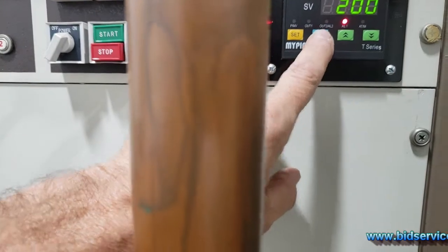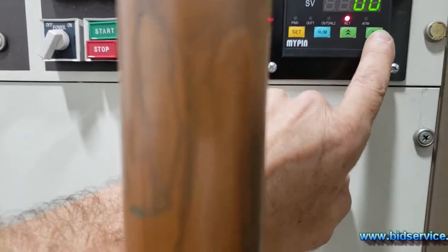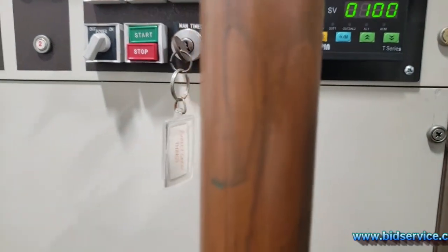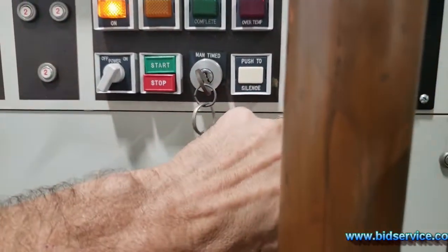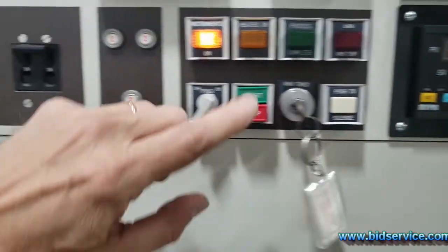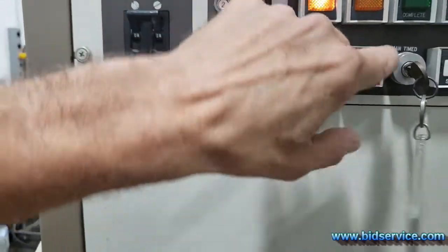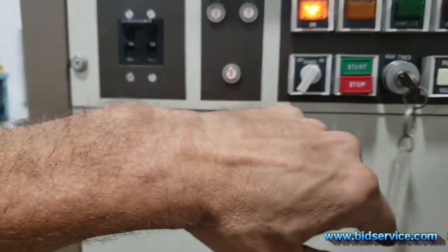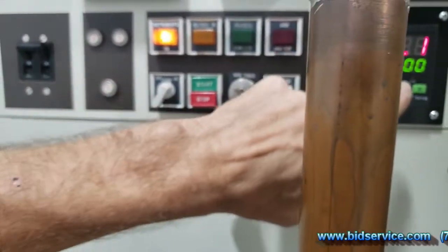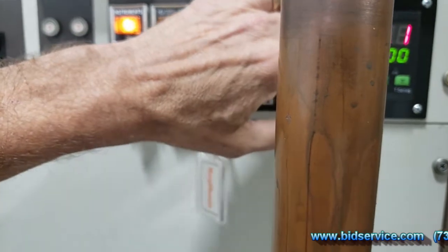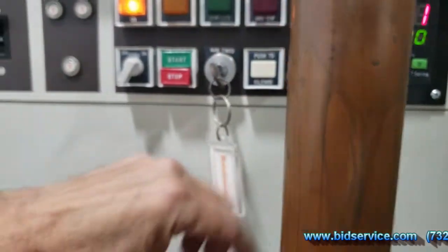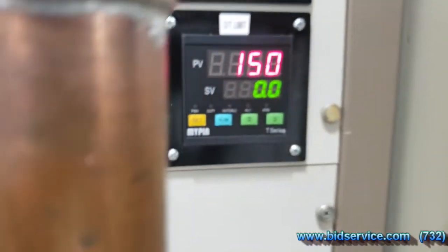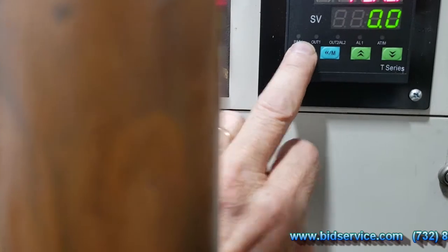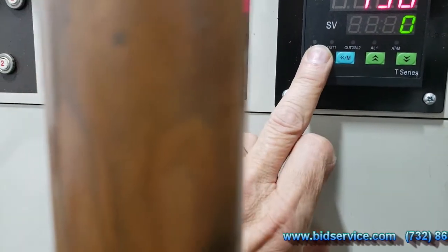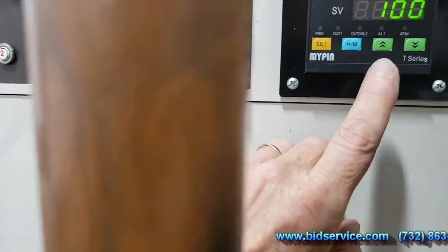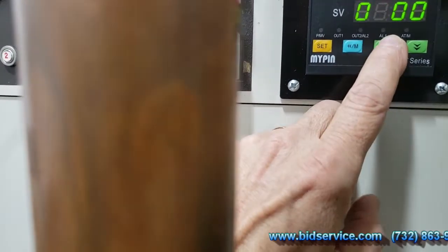If I were to drop this down to, say for instance, 100, go ahead and hit set. As you can see, we lose the alarm 1 light, at least on the outer over temp limit controller. And you see the heaters are now off, and by hitting start, they will not stay on. So that's just an over temperature protection. And again, both AL1 on the over temp limit and the temperature controller need to be lit in order for the start button to work. So what we'll do here is we'll go ahead and change this back to 200. Press and hold the set. Step over, 200, set.